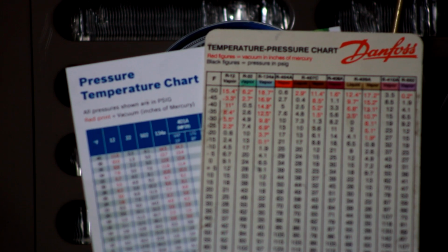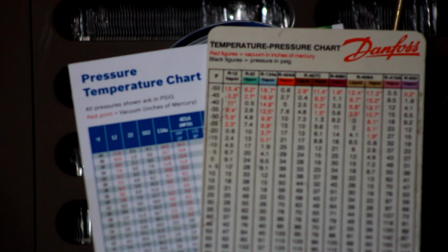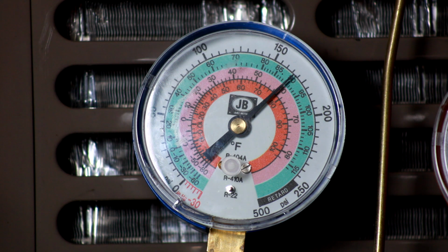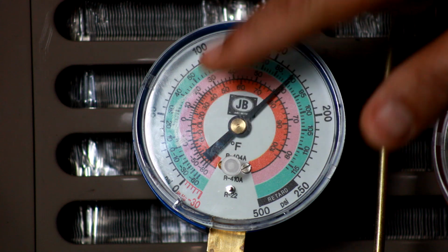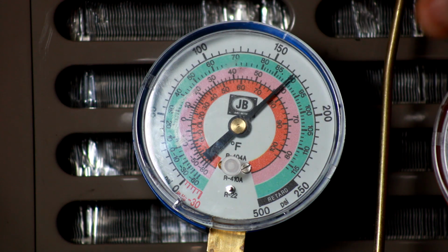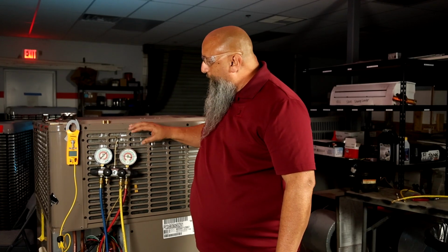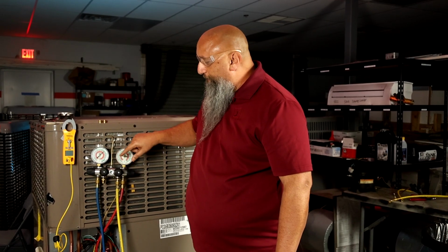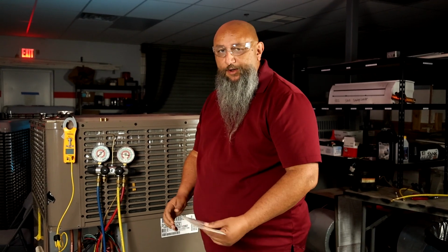Okay, so when we start talking about the temperature-pressure relationship, we have these handy little charts that a lot of us use, and I recommend you do have one. You keep one available. But for today's purposes, we happen to have a set of analog gauges that actually have the 410A refrigerant that we're using in this unit built in to the gauge, and that would be that pink circle. And obviously there's multiple refrigerants. The inner orange circle there is for 404A, and the outer circle is going to be for, I believe, R22 on this one. But you can utilize this analog gauge with the appropriate refrigerant on there and not necessarily need these separate temperature pressure charts.